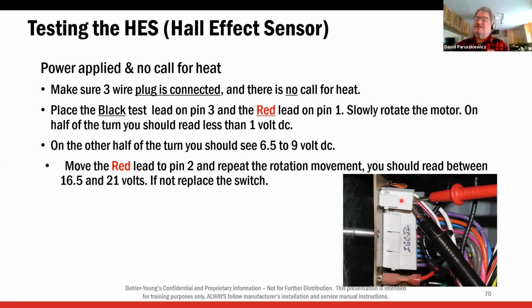Now, the Hall effect sensor is basically a generator. If you look at an older Bryant Carrier rooftop unit, say 20 years back, well, maybe not 20, but back a ways, there are 3 wires, black, white, and red, coming off the back of the inducer. And there's actually a sensor in there, and a magnet that spins, and it actually measures motor speed. It's not a switch, it's a sensor.